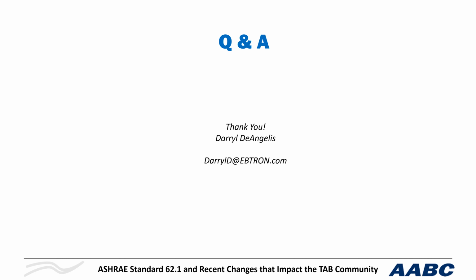All right. Third question. Are there certain spaces or buildings that require use of the IAQ procedure versus the VRP? That's a very good question. Again, the ventilation rate procedure is based on normal sources of contaminants. Certainly, COVID is not a normal source, and a lot of these design compounds may not be normal sources. So the rates in 62.1 are for these normal sources. If you have something that is an unusual or abnormal source, that would be a good time to use the IAQP. If you have spaces that are unique because of the chemicals they have or the process they have in place, that's a good time to use the IAQP as opposed to the ventilation rate procedure. But the standard allows you to choose which path to go.